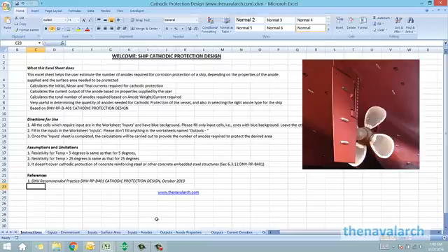Basically there are two types of calculations being done here. One is to calculate the total mass of anodes required to protect a given surface, and the other is to calculate the total current required. The user needs to provide some inputs, and then based on these inputs and the formulas provided in the DNV RPB401, the spreadsheet will do the calculations and give the final number of anodes.